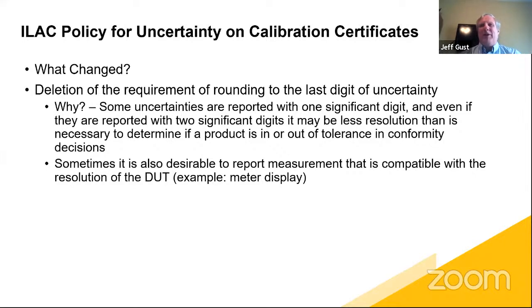If you calculate, and we do this all the time at Fluke as well, sometimes our estimation of uncertainty might be a shade better than our CMC. But if that's the case, then we report our CMC value. What we do is we keep that documentation, we keep that data, and the next time the assessor comes in, we show them, here's a real life situation, real measurements that we made, and we can use that data to reduce our CMC further so that we don't have that overlap next time. But again, yes, your process needs to be such that if your computed CMC is smaller than your scope CMC, then you need to report the scope CMC. And you're right, it may affect your TURs, but it is what it is. Your CMC is the best capability that you have been determined to be technically competent to.